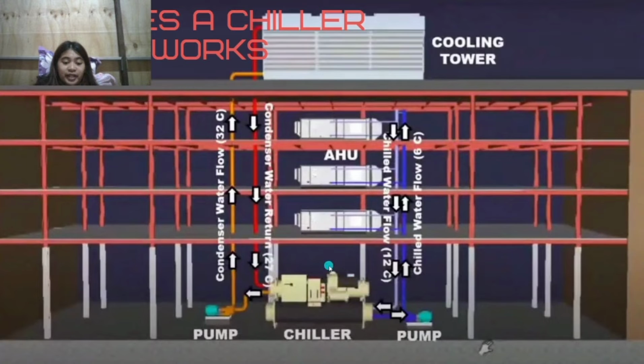The chiller is the producer of the chilled water in the system. It has two main cylinders, the evaporator and the condenser. The heat is collected and sent to the cooling towers. The evaporator is on the chilled side, where it is insulated to keep the cool inside. A compressor is placed on top of the evaporator together with the power supply and the control to the system. The illustration below is a centrifugal chiller used by the wine warehouse. The chilled water leaves the evaporator and it is pulled out by the pump.